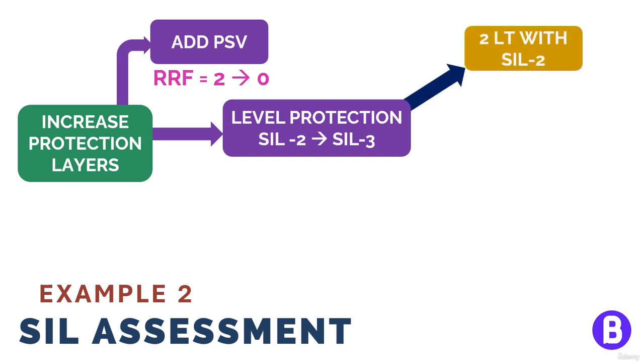Only the level transmitter had a SIL rating of 2. So in order to increase the SIL rating of the SIF function, we shall need at least 2 transmitters with SIL 2. It's very rare to consider a level transmitter or any transmitter with SIL 3. That's why in this case voting would be the alternative. So we can consider 2 level transmitters with SIL 2.